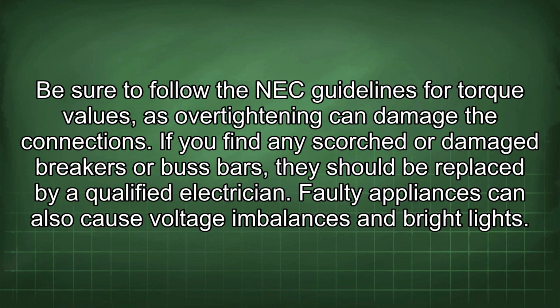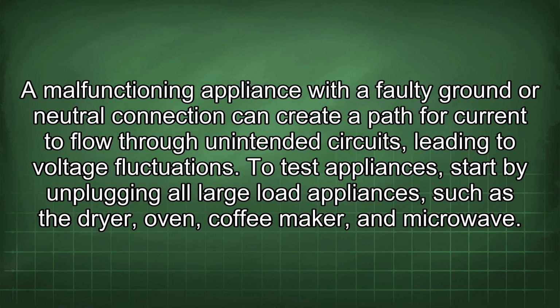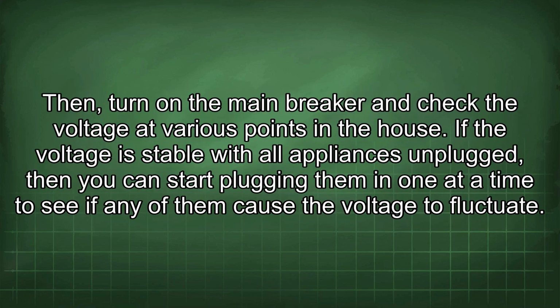Faulty appliances can also cause voltage imbalances and bright lights. A malfunctioning appliance with a faulty ground or neutral connection can create a path for current to flow through unintended circuits, leading to voltage fluctuations. To test appliances, start by unplugging all large load appliances, such as the dryer, oven, coffee maker, and microwave. Then turn on the main breaker and check the voltage at various points in the house. If the voltage is stable with all appliances unplugged, then you can start plugging them in one at a time to see if any of them cause the voltage to fluctuate.